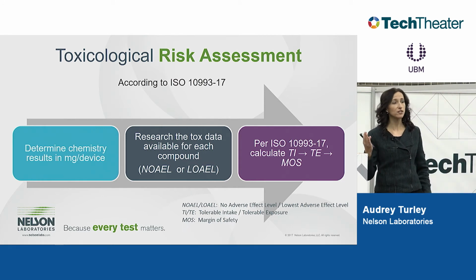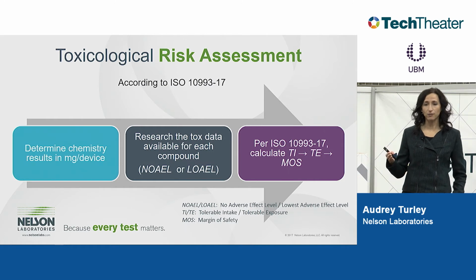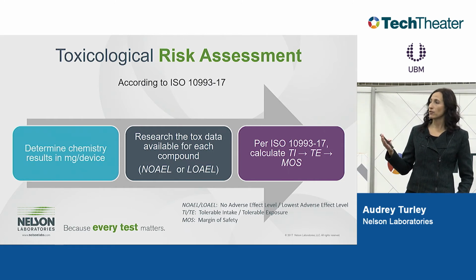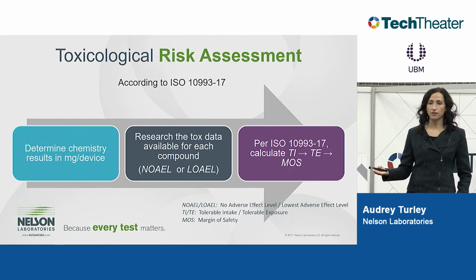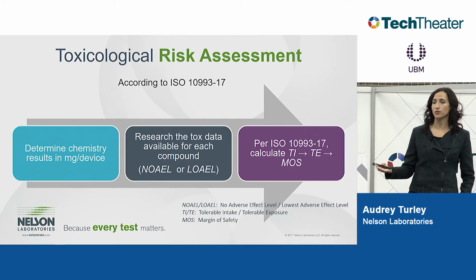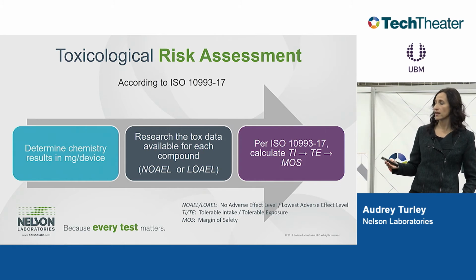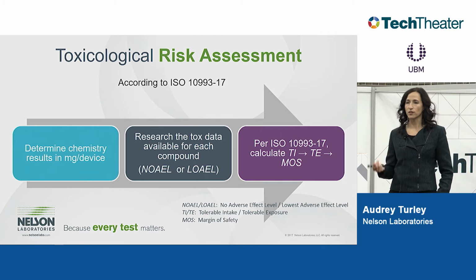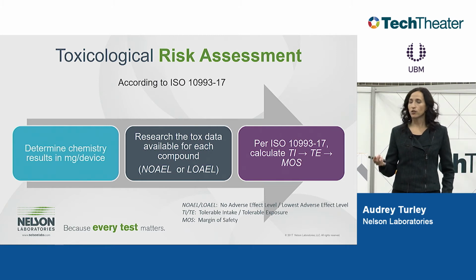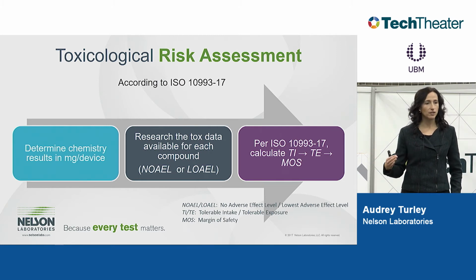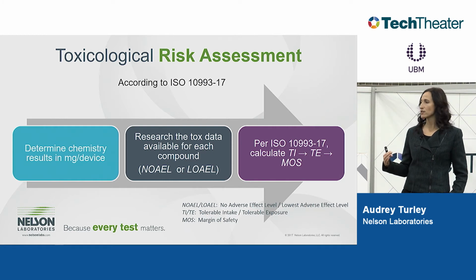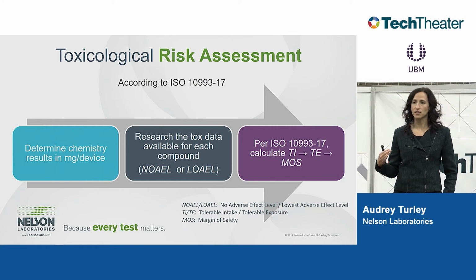already published. This is where you save some time in animal testing as well. If you do this, you can already use animal testing that's been performed and published for the specific compounds that you found on your device. So this really relates well to your actual device. And we're looking for NOELs or LOELs. We'll look for reference doses as well. But NOELs and LOELs are levels that are established in experimental tests where no adverse effect was seen on the subject animal.